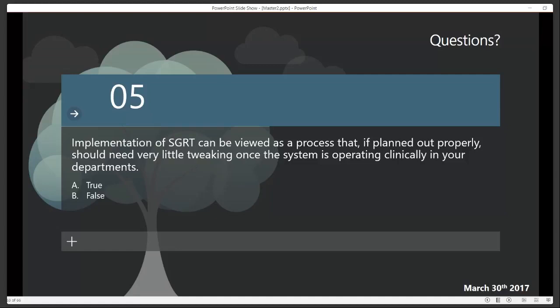In the case of body sites, there are questions coming in and I can't read fast enough. Have you had any operational issues with Align RT? I've not had operational issues per se with Align RT. I have had issues. I had an FPGA that went bad one time, which caused the way Align RT works in the 3-camera system is there's a master and 2 slaves, and you have 2 frame grabbers for 3 cameras. And so some cameras and some FPGAs do not play nicely as the master, and so we had to swap cameras until we could get the FPGA issue figured out. But operationally, it worked just fine. It was just that we had to change the configuration until we could figure out what the issue was.